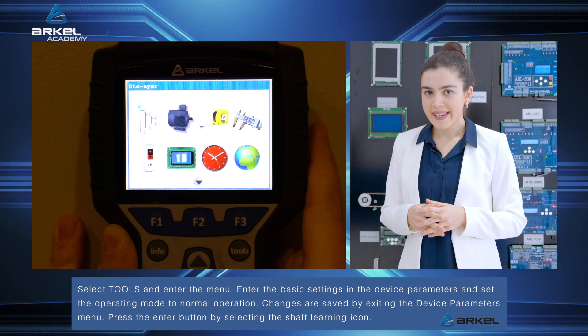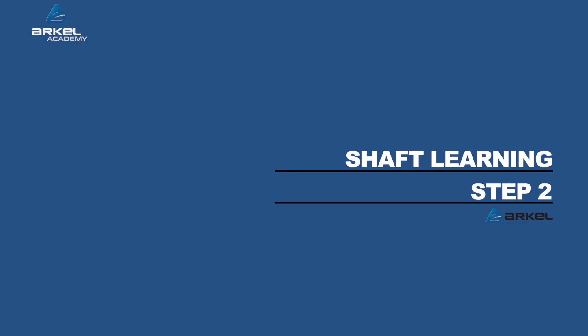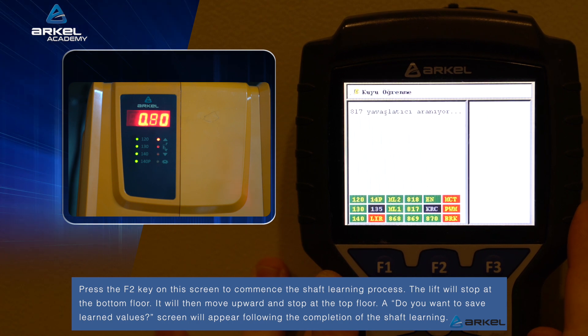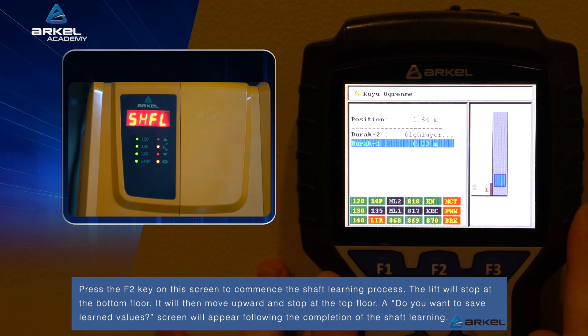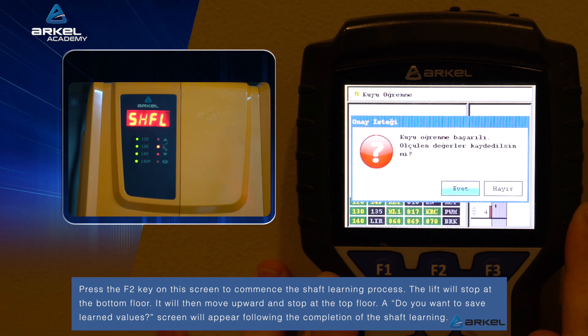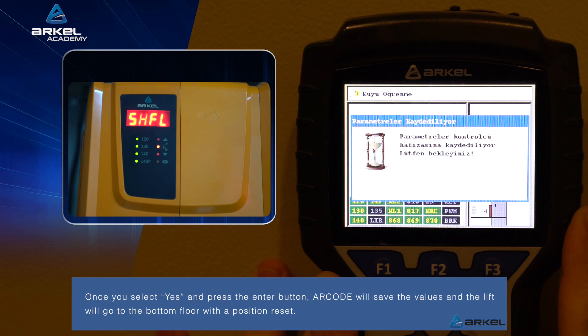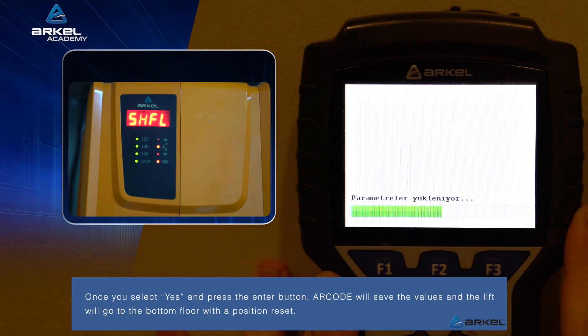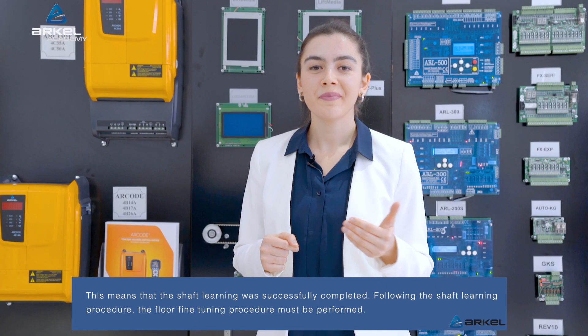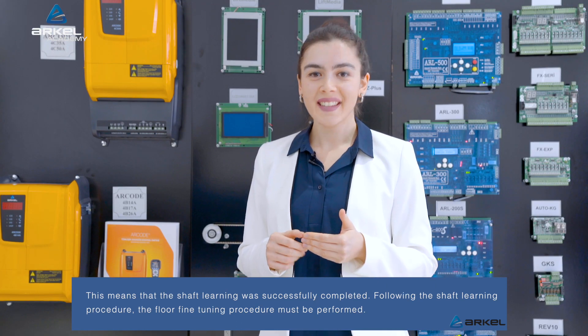Press the enter button by selecting the shaft learning icon. Press the F2 key on this screen to commence the shaft learning process. The lift will stop at the bottom floor, then move upward and stop at the top floor. A prompt asking whether you want to save the learned values will appear following the completion of the shaft learning. Once you select yes and press the enter button, ARCODE will save the values and the lift will go to the bottom floor with a position reset. This means that the shaft learning was successfully completed.